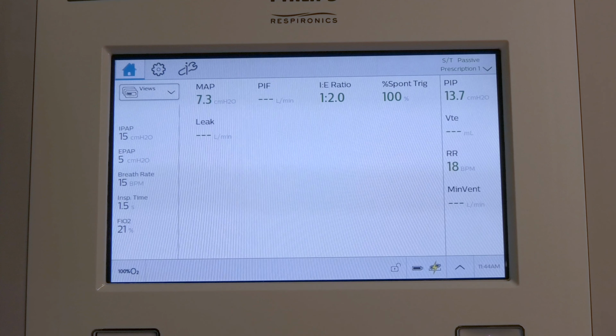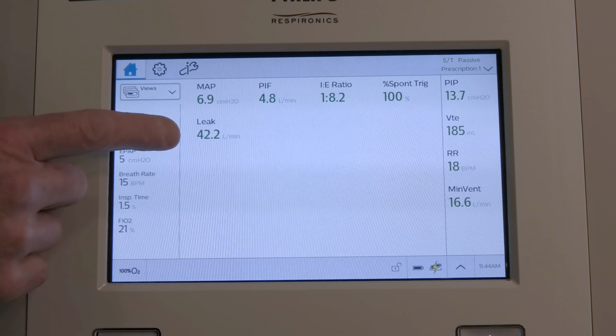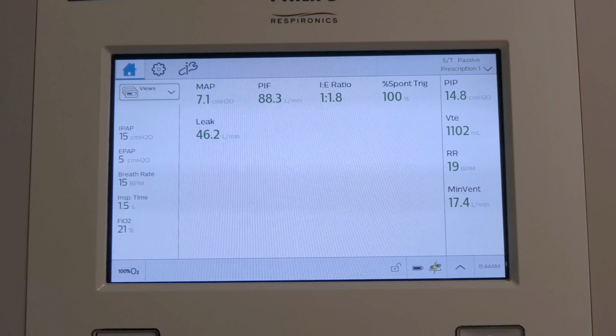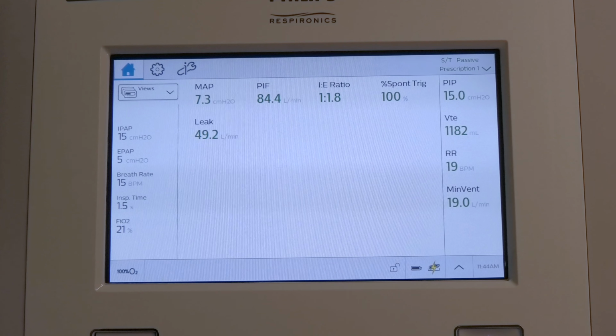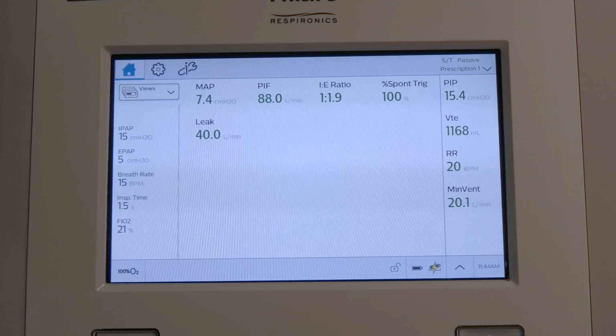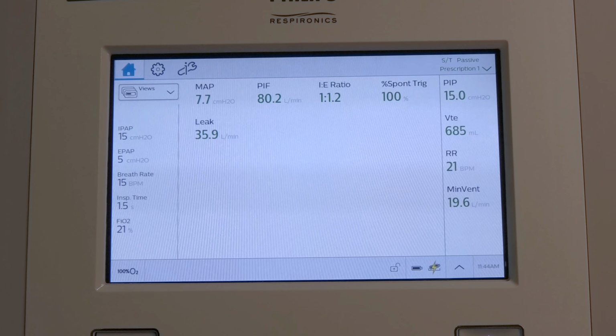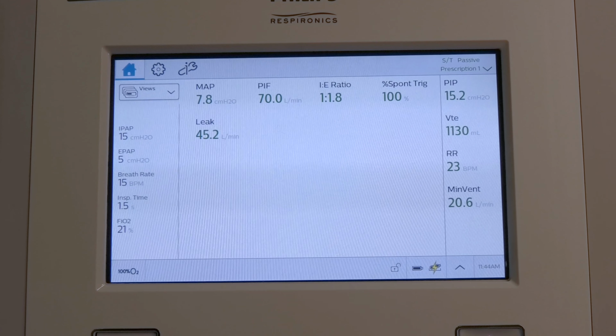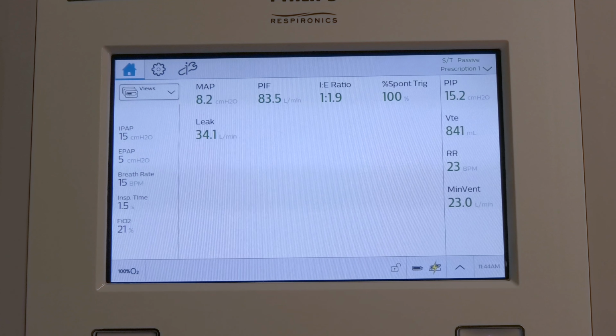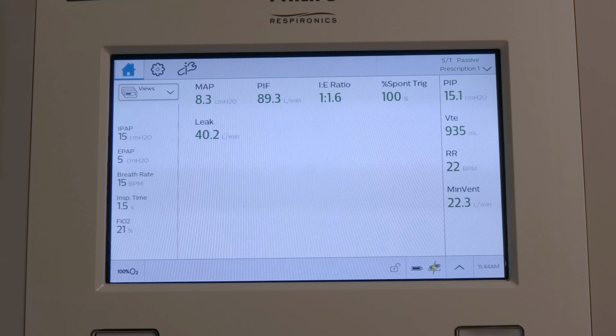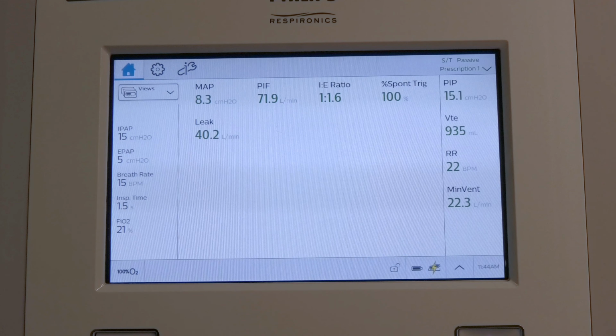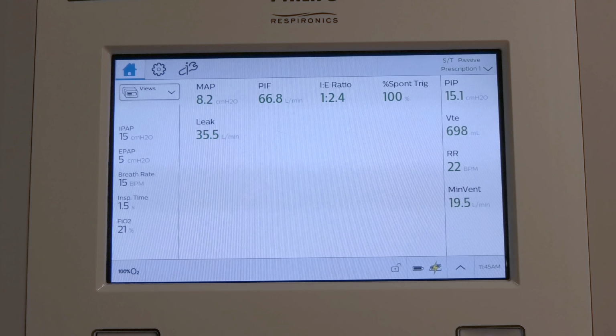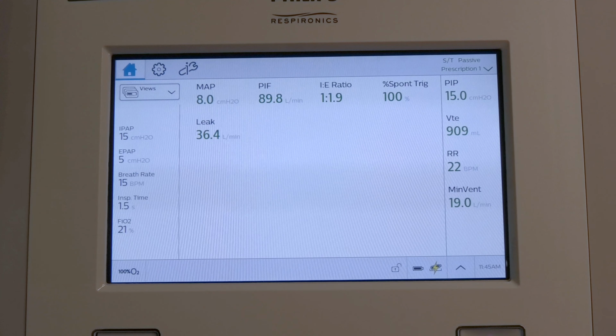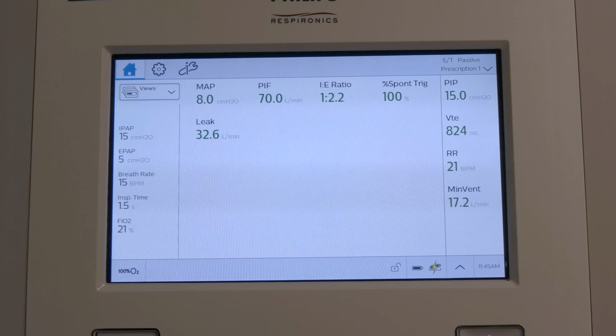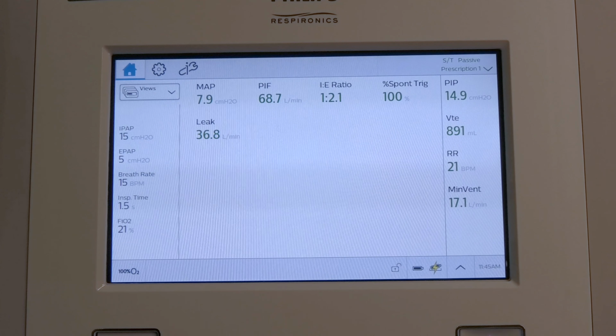The things that we're interested in are how much leak we've got. So we want our leak to be relatively low. The ventilator will compensate up to a leak of 60 litres a minute. In COVID-19, we try to keep the leak as low as possible so we don't have non-filtered exhaled gases circulating around. But we set the leak for patient comfort also. The mask can't be too tight, otherwise the patient won't be able to wear it for very long. They won't be able to comply with the therapy. So a leak of between 7 and 25 litres is probably about perfect.